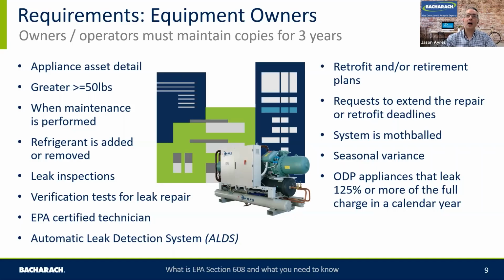And it's regarding high leakage of that equipment in a calendar year. And a calendar year is 1st of January to 31st of December. So if you have a refrigerant HVAC appliance that's got more than 50 pounds of refrigerant, that's used over 125% of its charge, so simple maths, it's got 100 pounds in it, and in that calendar year it used 125 pounds of refrigerant added back to it, you have to report that to the EPA within 2 months of the following calendar year.